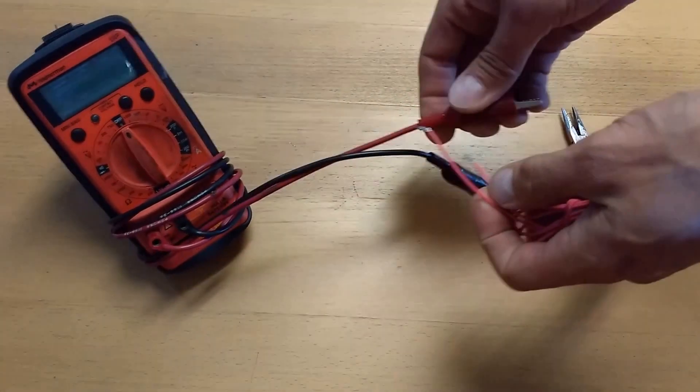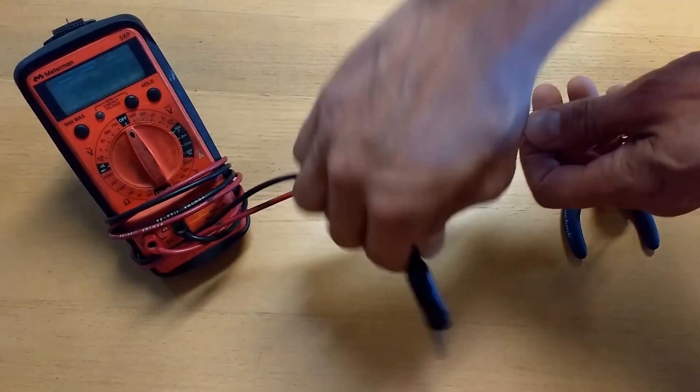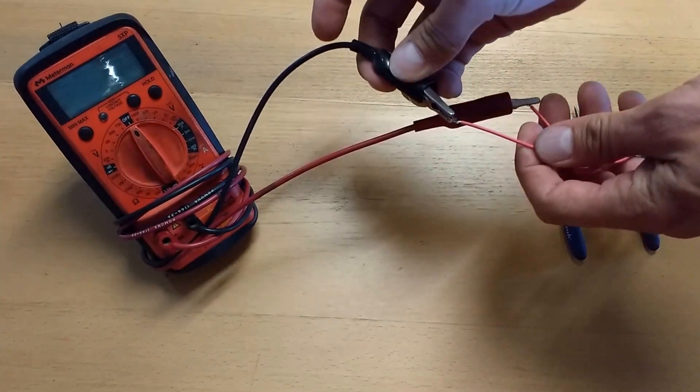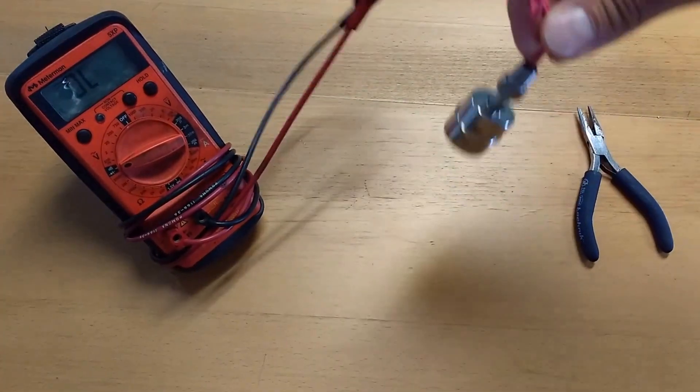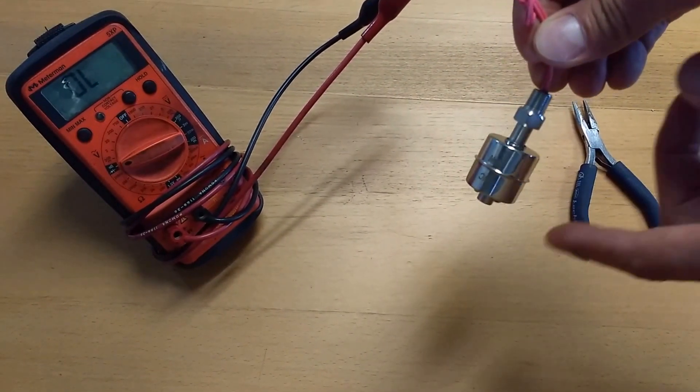First we will hook up our multimeter. Turn it on to continuity and you can see when the float is in the down position it's normally open.